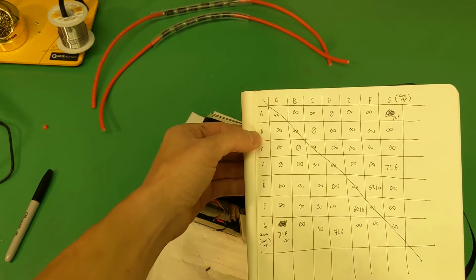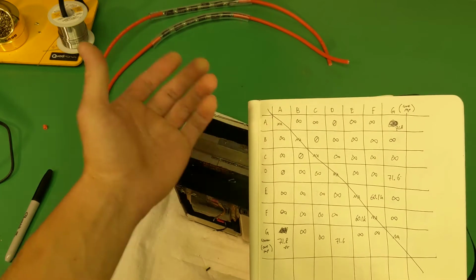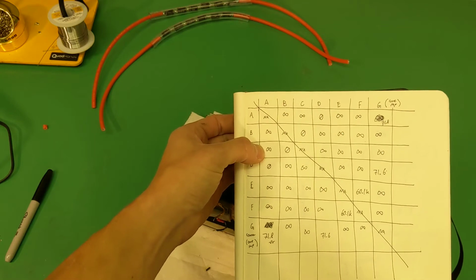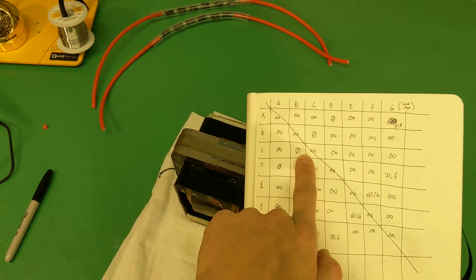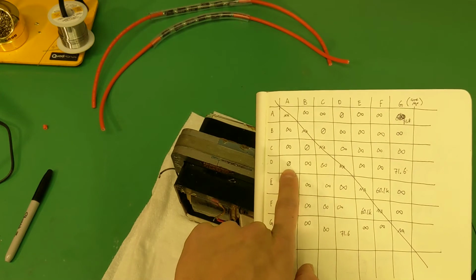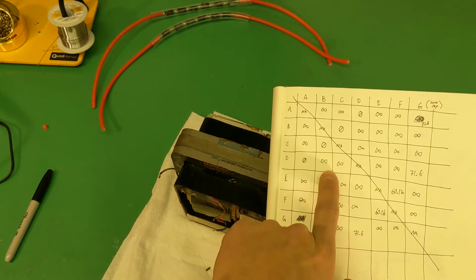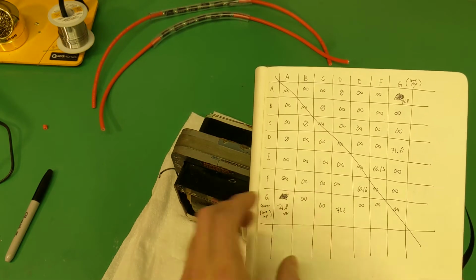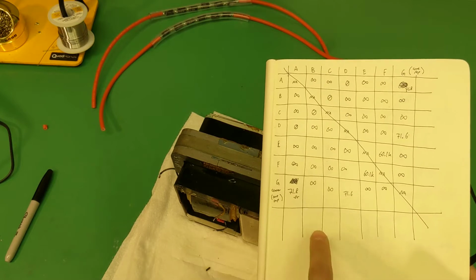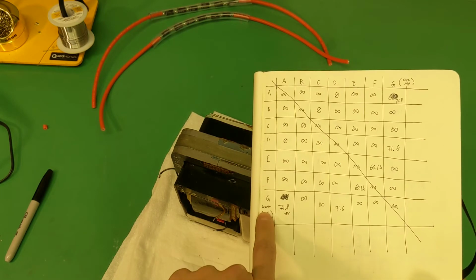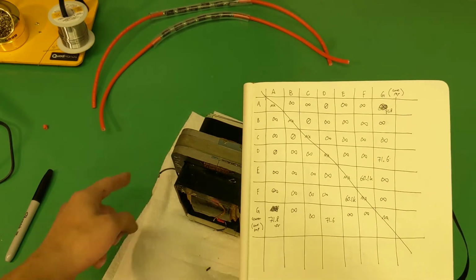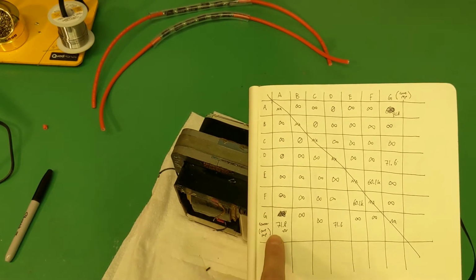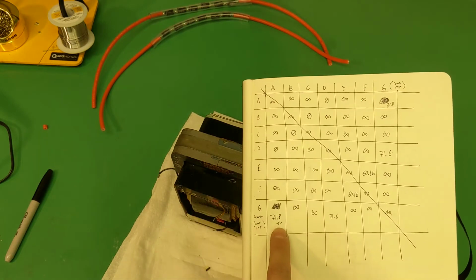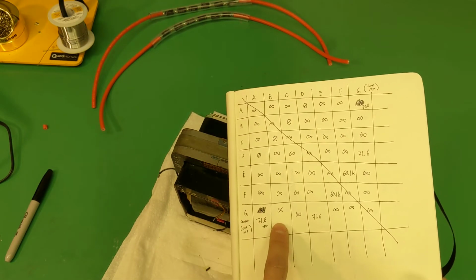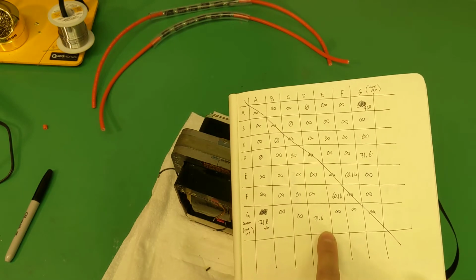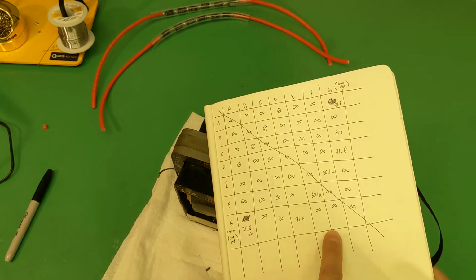From terminal A to B we had infinity ohms, so no connection. A to C had no connection, but B to C was a short, 0 ohms. D to A was 0 ohms. B to D had no connection, and so on through the entire process, with some interesting results. For instance, the last ground connection, the G connection, is the center tap wire on this side. G to A measured 71.8 ohms, no connection to B or C. G to D was also 71.6 ohms, and no connection to E or F.